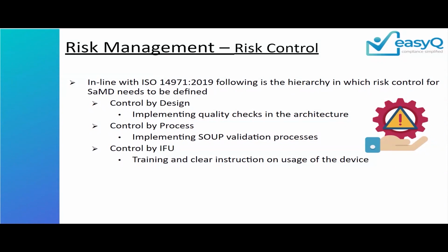Similarly, for medical devices, for certain key critical activities, there might be certain pop-ups, cautions, and warning messages that are part of the product, right? Even those warning messages are part of IFU, as is the training that you might be giving to the end users on how to use the product. So any mode of information that you give to the end user to ensure that they use the product in the correct manner is information for use, right?